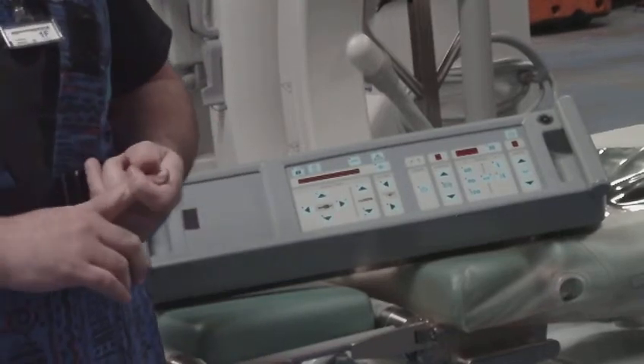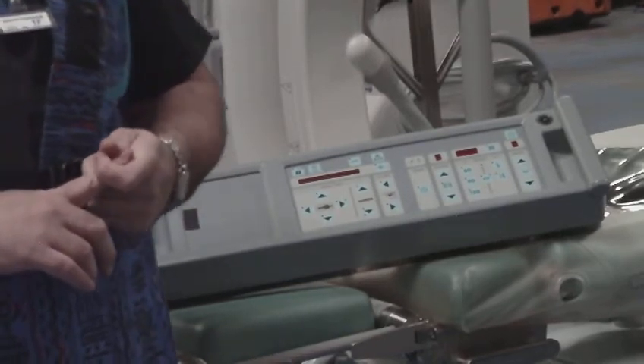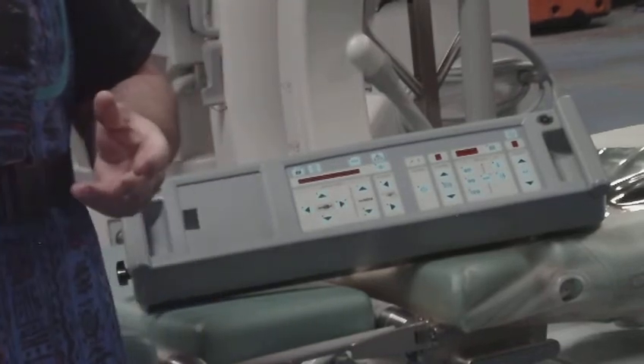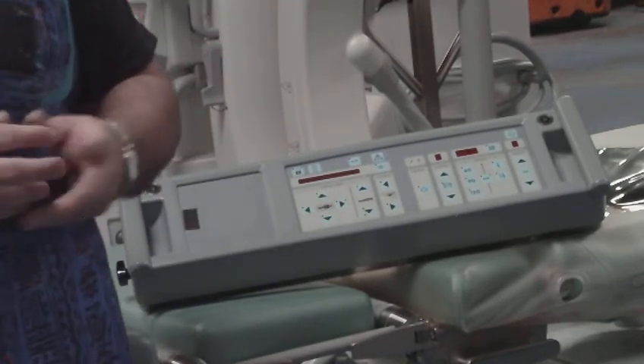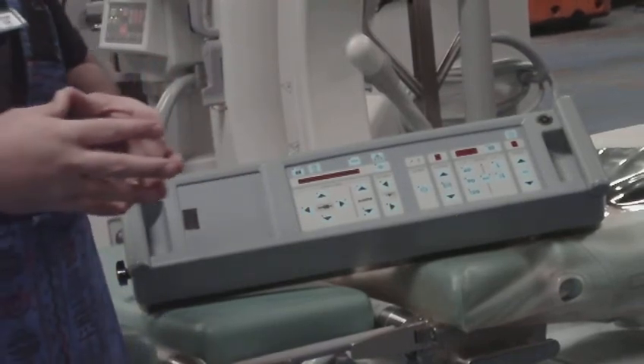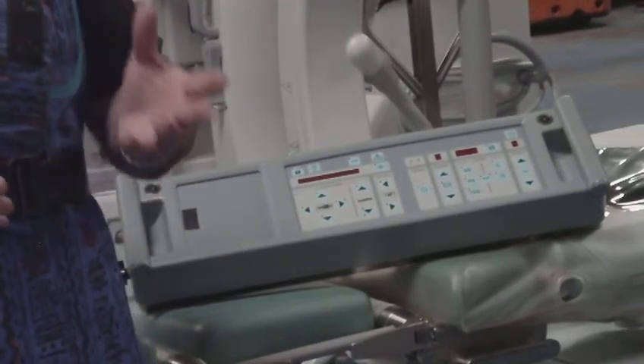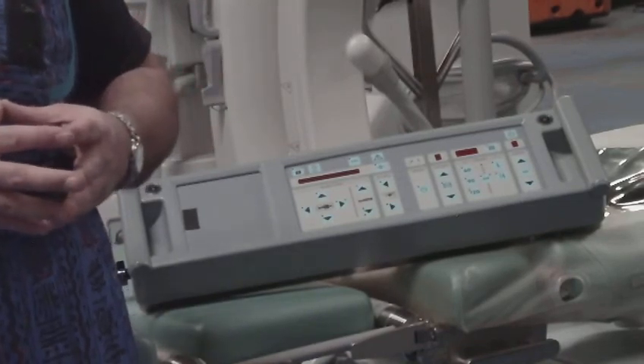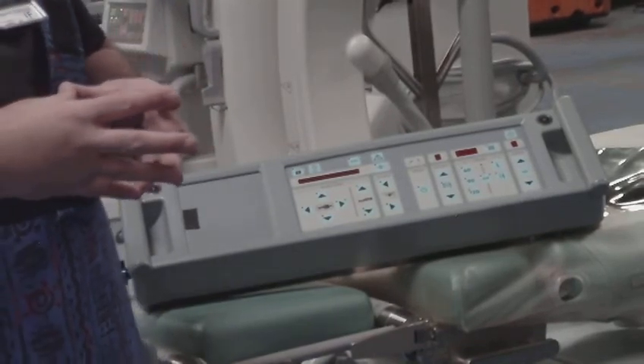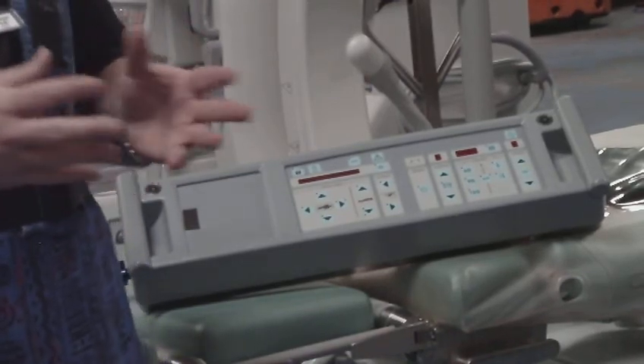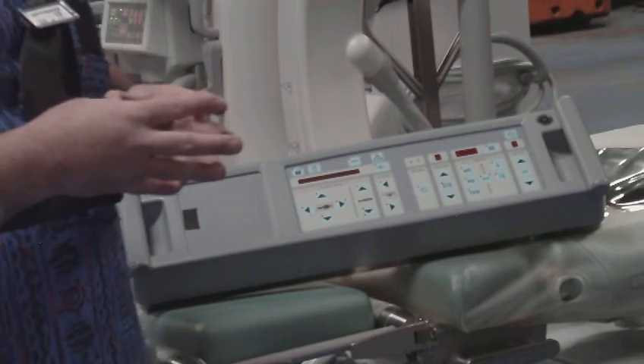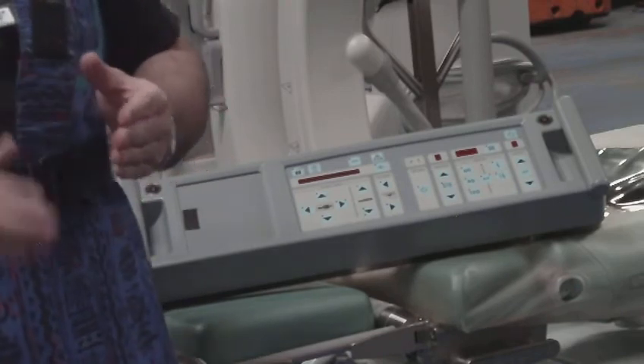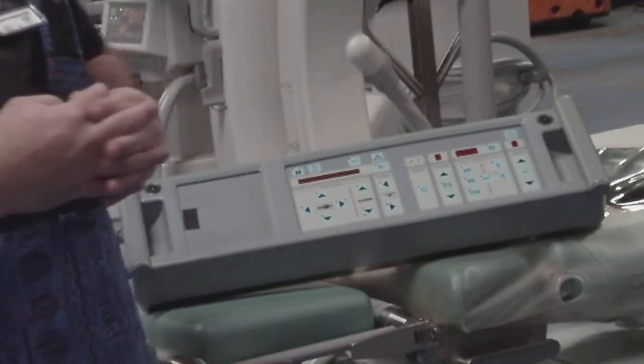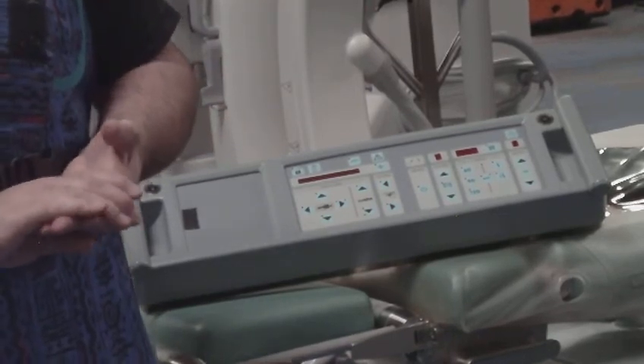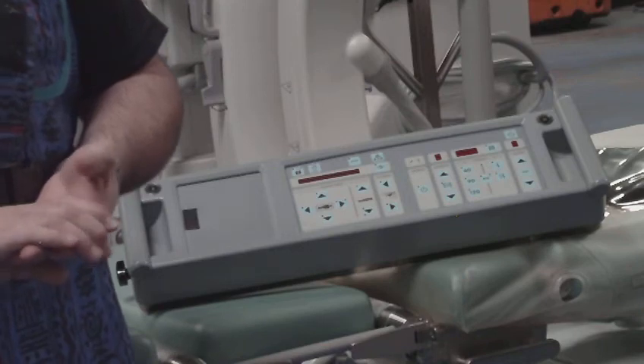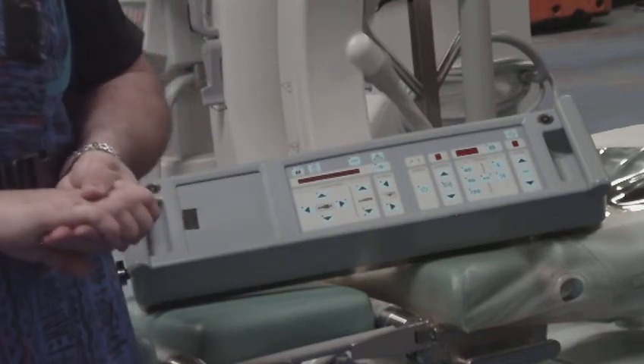You don't want to go over level 7. Well, you can go to level 8, but most stones that are in kidneys will break up at level 7. If you have to go to level 8, it's acceptable, but more risky. Don't ever go to level 9 for renal stones. If they're in the ureters, level 9 is fine, but stay at level 8 or less for a renal stone. You can deliver 3,500 shocks for level 7 in the kidney. Level 8, you can only deliver 3,000.